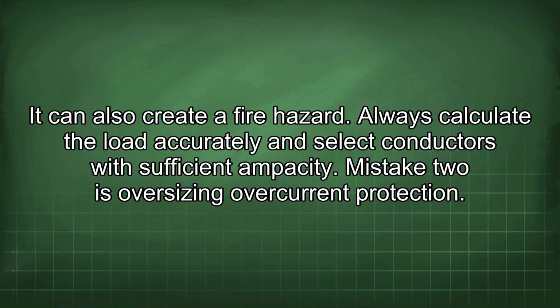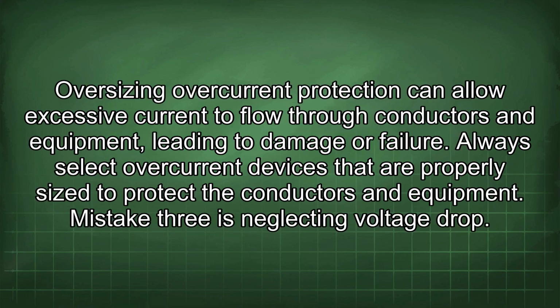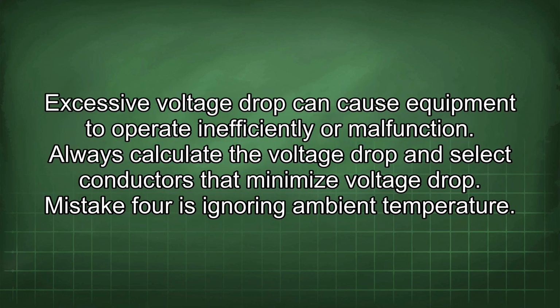Mistake 2 is oversizing overcurrent protection. Oversizing overcurrent protection can allow excessive current to flow through conductors and equipment, leading to damage or failure. Always select overcurrent devices that are properly sized to protect the conductors and equipment. Mistake 3 is neglecting voltage drop. Excessive voltage drop can cause equipment to operate inefficiently or malfunction. Always calculate the voltage drop and select conductors that minimize voltage drop.